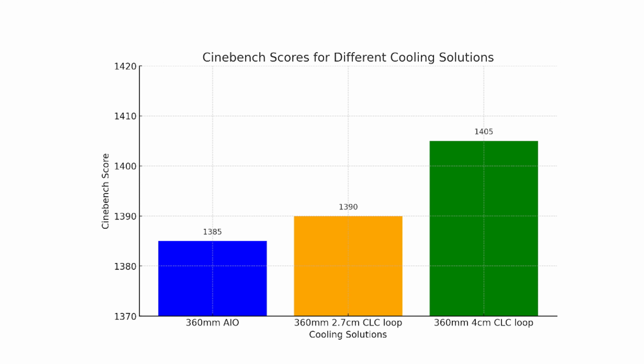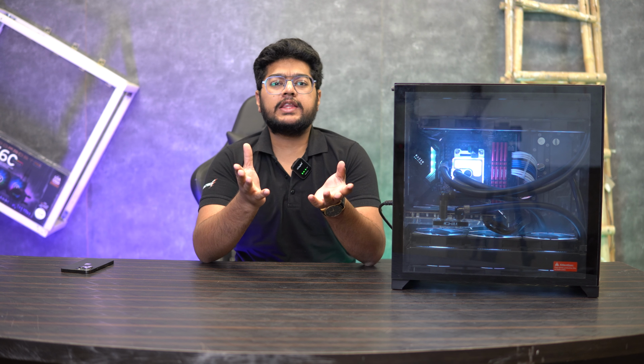All our testing has been done, and now all the results are on your screen. Coming to the conclusion: does the thicker radiator make a lot of difference? In a way, it does. We cannot neglect the fact that increasing the thickness of the radiator saves a few degrees, and it's the only way to increase and optimize your cooling solution in a cabinet where you cannot add more radiators to increase the surface density of a thin stack. So increasing the thickness is one of the only options left.